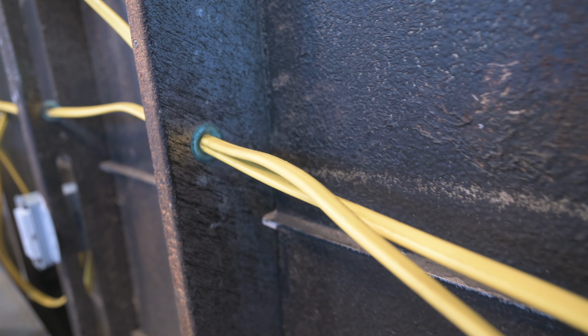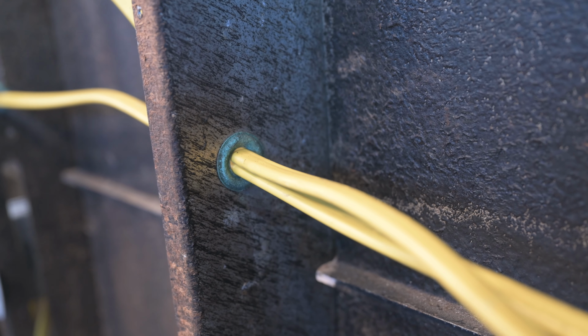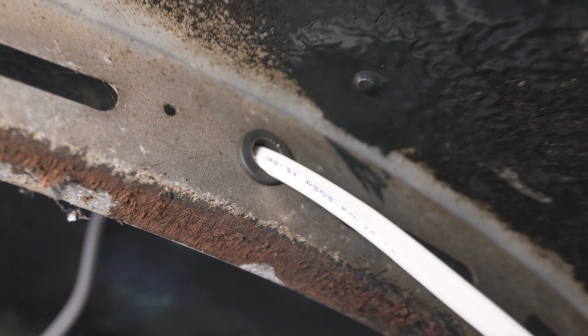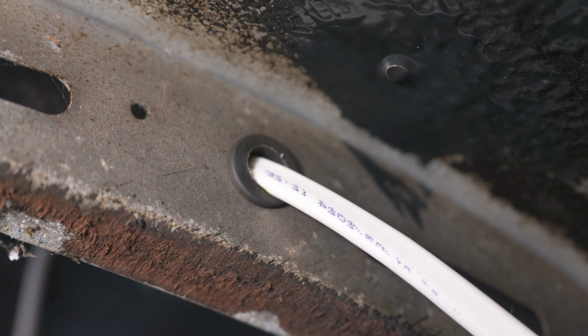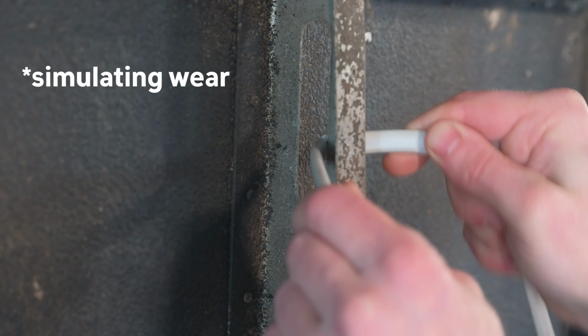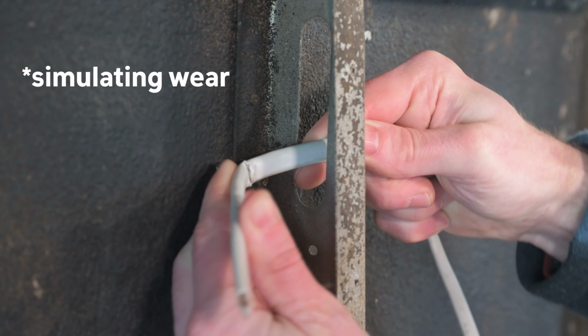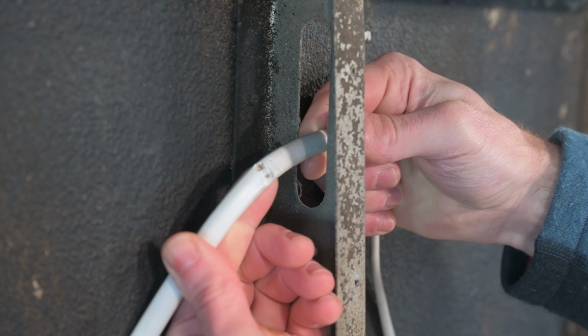Preferably we pass cables through holes like these that have metal grommets. When there aren't any, we put in little rubber grommets. If you don't put a grommet, over time and because of vibrations, especially if you're on the road, these metal edges could eventually cut through the insulation and reach the wires inside. If you don't have the trailer grounded, you could get shocked. But ideally, it would just cause the breaker to trip, but you would have no idea where to look since these will be buried in the walls.